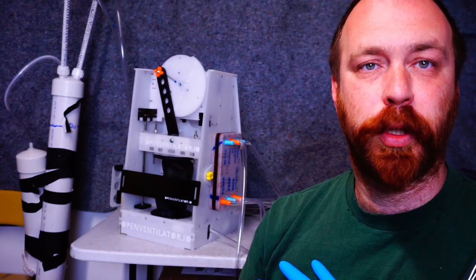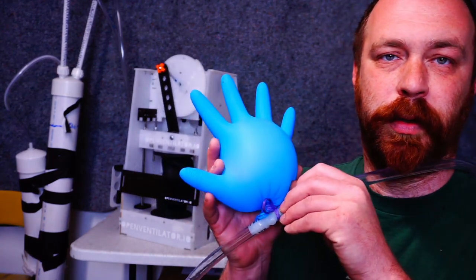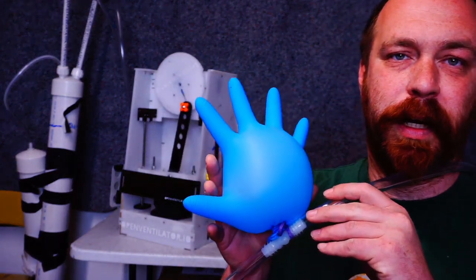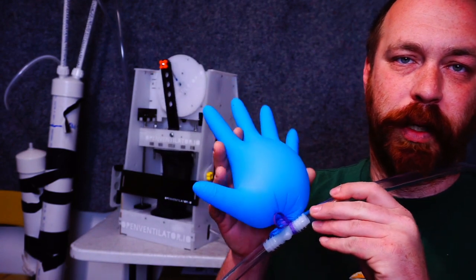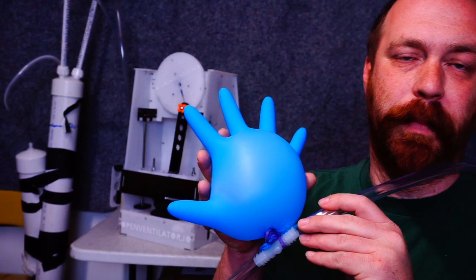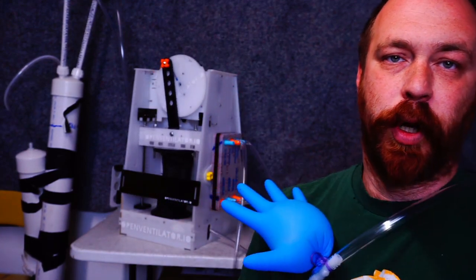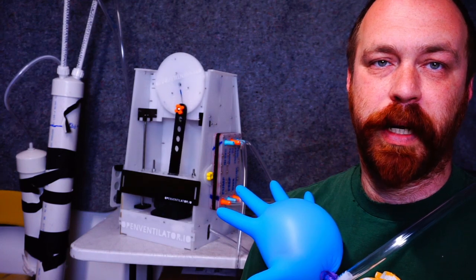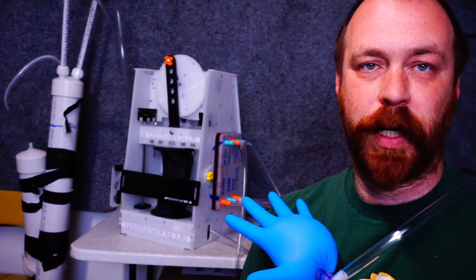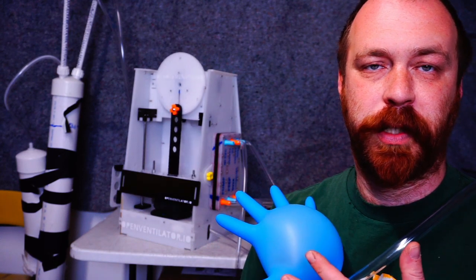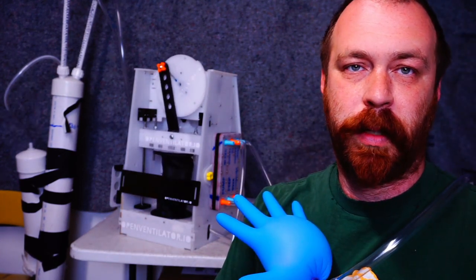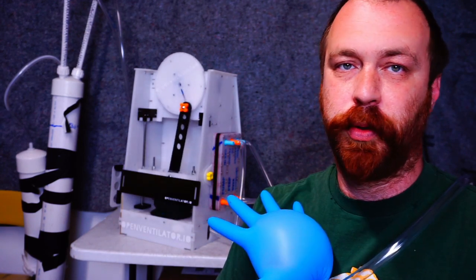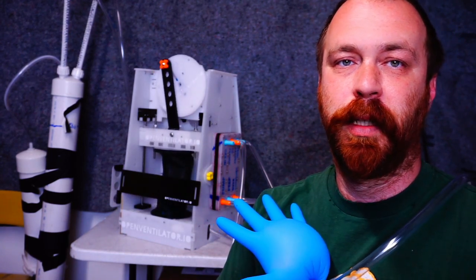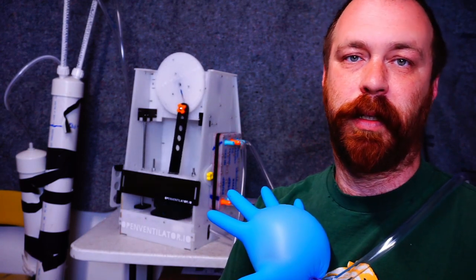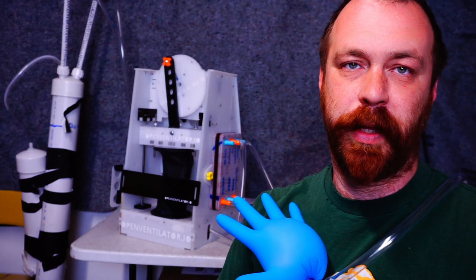It also has the ability to control PEEP pressure, which is positive end expiratory pressure. So you can see this balloon is inflating and deflating, but it never fully deflates. That's because it only deflates up until the point where it has the set PEEP pressure. It also has an overpressure control, so that the pump can never break a certain set pressure while pumping into the patient's lungs. Also, the ventilator has an autonomic inhale bypass, so that if you have a patient who, let's say, yawns during the exhale cycle, they can breathe around the machine and still inhale during the exhale cycle.